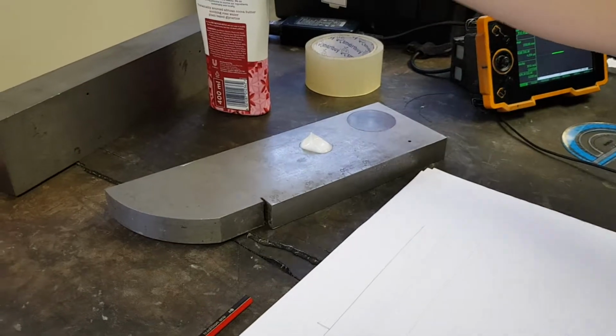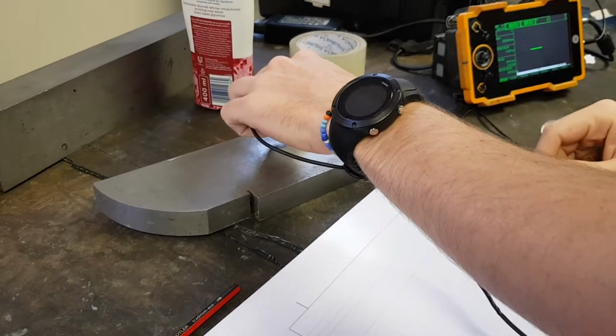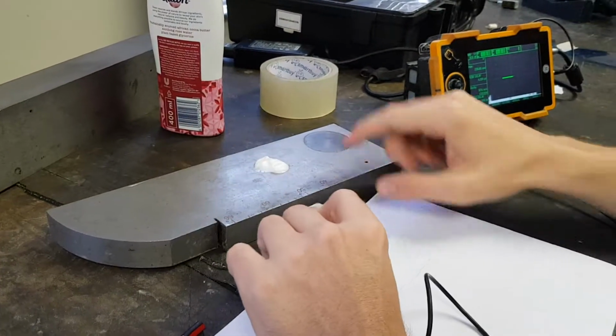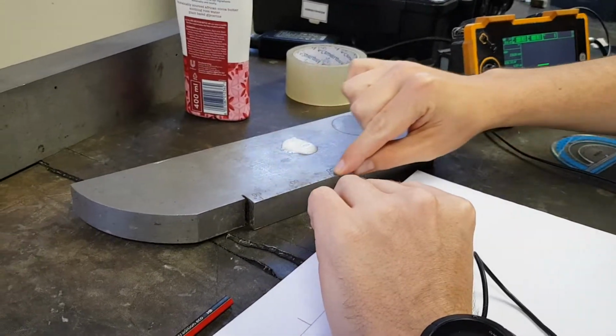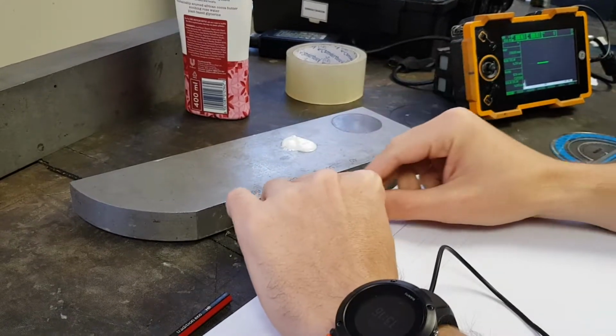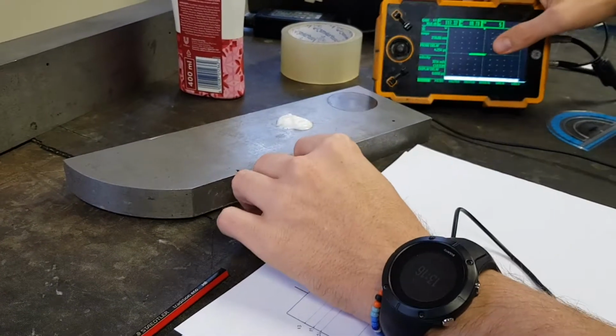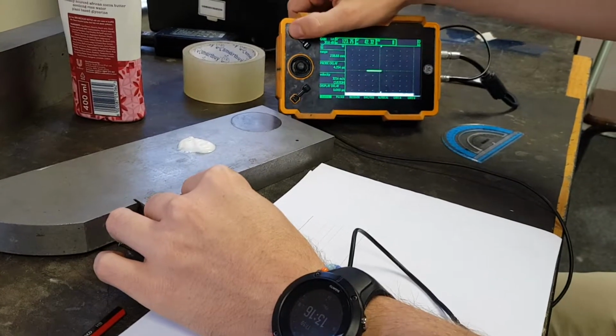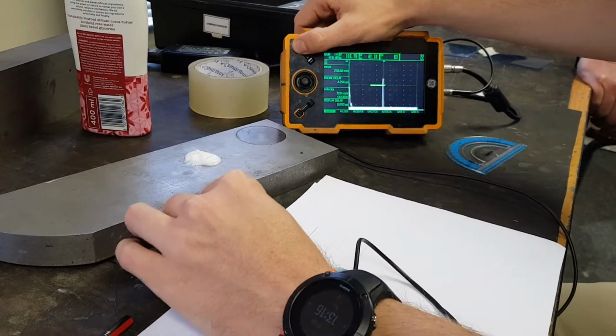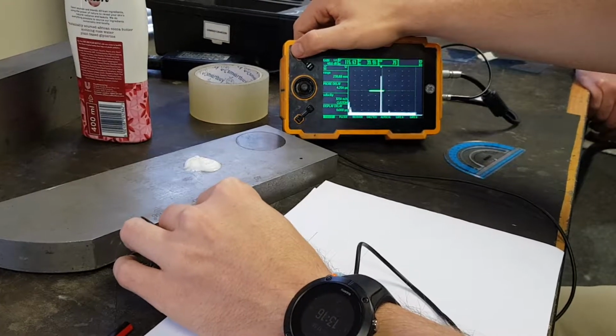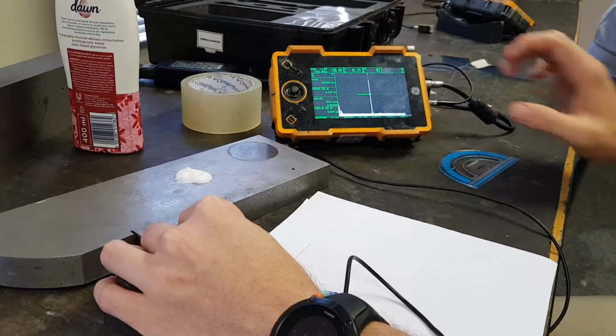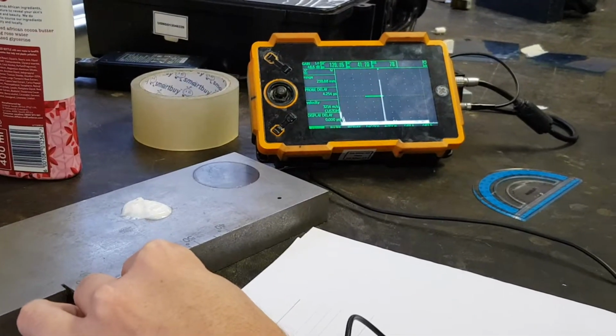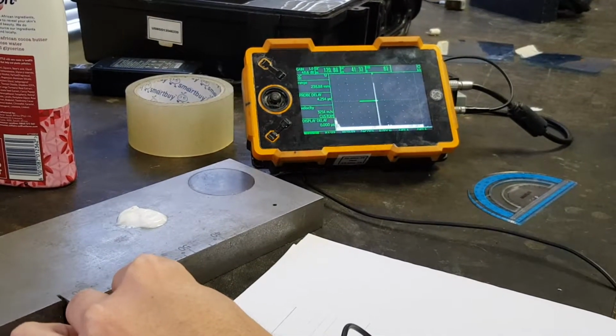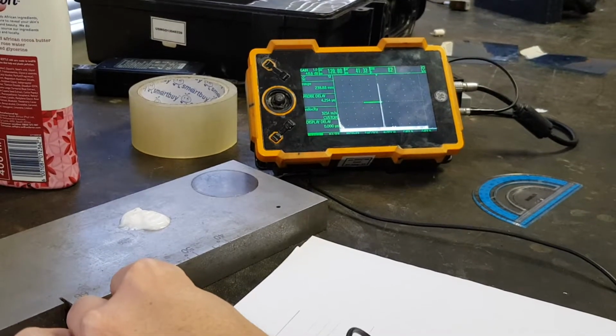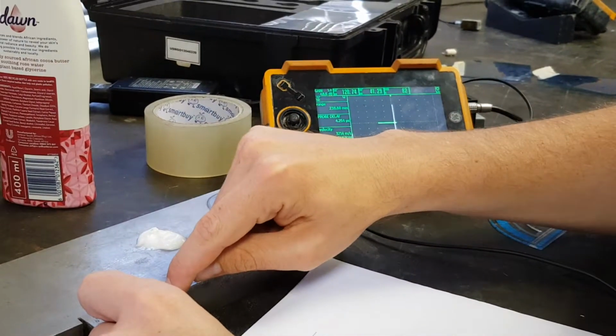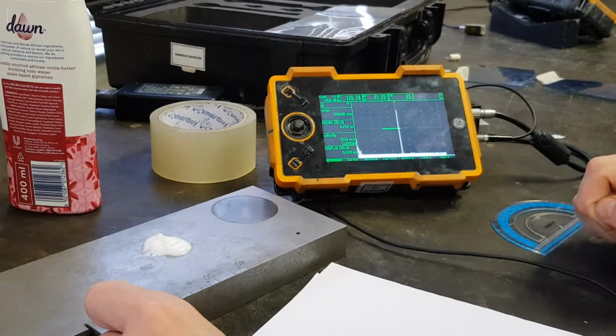All right, part one. We're doing an angle check. So we'll just place our probe, take a little bit of couplant, and you'll notice here on the V1 block, a couple of angles are written down there. So all you're going to do, you put your probe on there, calibrated 60-degree probe, add a couple of dB so you can see the echo correctly, and as you increase it, you just maximize it, find the maximum, and where the maximum is, you can read what angle your probe is.